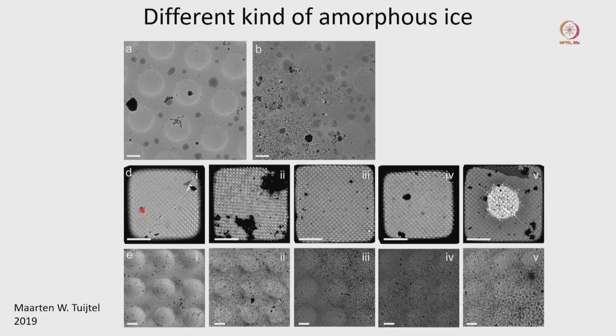So when we have this kind of ice pattern, if you have a broken ice, a broken square like this, it is better to avoid this kind of square, because if the z height, or eucentric height, is not accurate, it will be very difficult to get a properly focused image. I hope you remembered all of this. If the eucentric height changes, your focus is going to be affected. You have to pay attention.